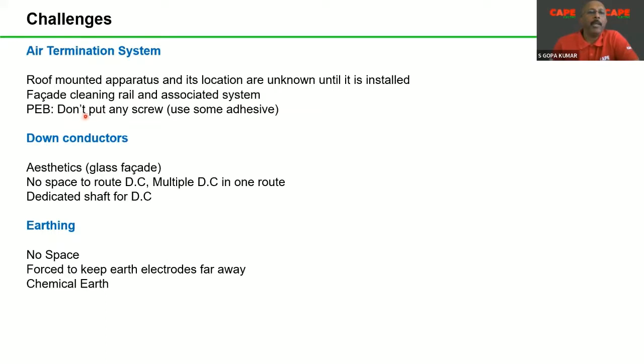Then in PEB buildings, one of the biggest challenges which we always face is the usage of screws. Don't use any screw, don't put any hole, use some kind of sticking material, adhesive material. So with an adhesive, you connect your conductor holders into the RCC. Please understand that these adhesives have certain life, probably 5 years or 7 years. After 7 years you have to replace it. And more than that, by using adhesive, you are isolating lightning protection, and in case of any strike, there will be spark over across the adhesive tape. So that means the effectiveness of lightning protection is gone.